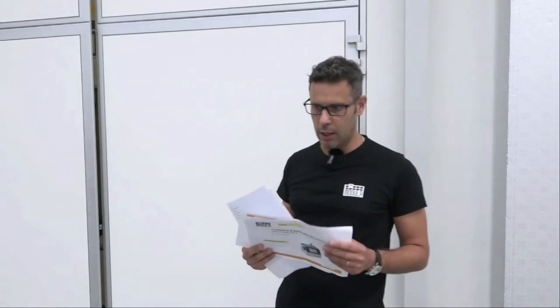A clean room is a room where inside we have a very small number of particles of a defined size, and this number is lower than a value written in the regulation. We followed the European regulation in this project, which is ISO 14644, that identifies a classification from ISO 1 to ISO 9. There's a correspondence with the American regulation, which has a classification from class 1 to class 1 million.